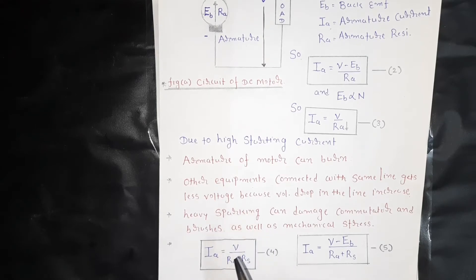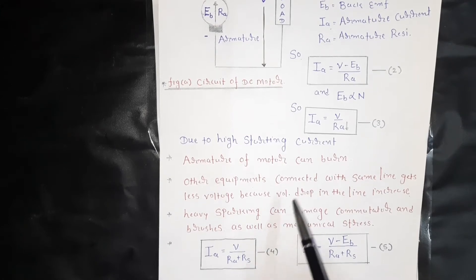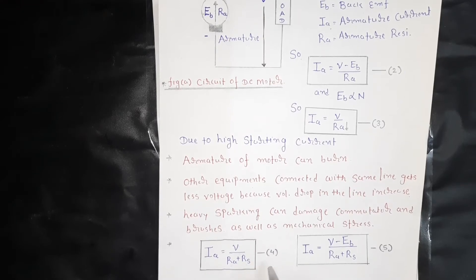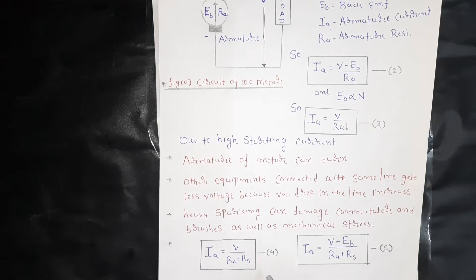What is the function of the starter? We use a starter to limit the starting current. What we have to do is described by equation number 4: IA equals V divided by (RA plus RS), where RS is the starting resistance. By using a starter, we add an external starting resistance in series with the armature.